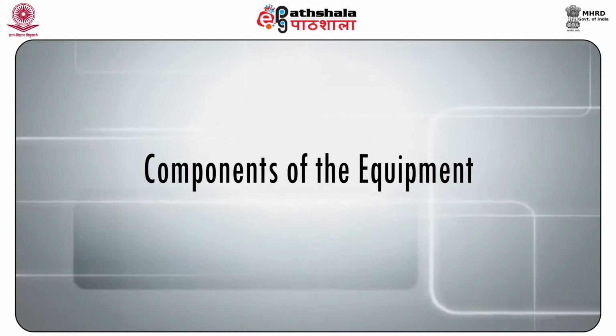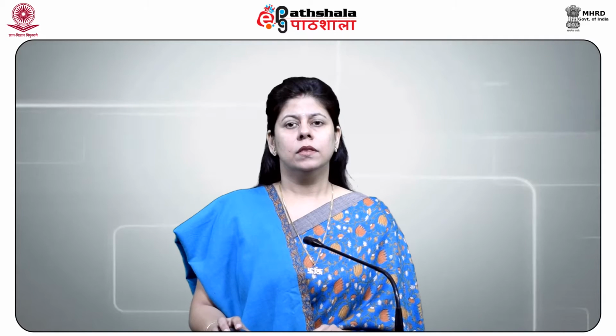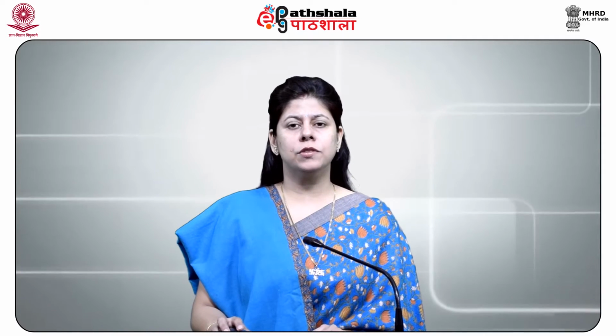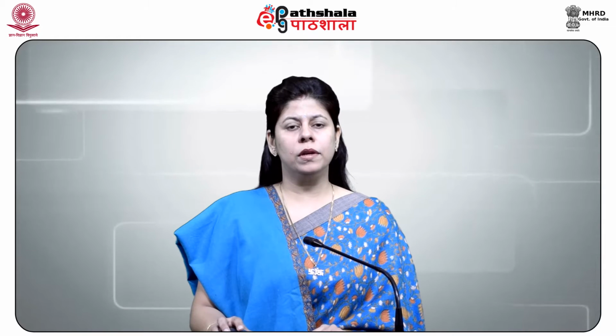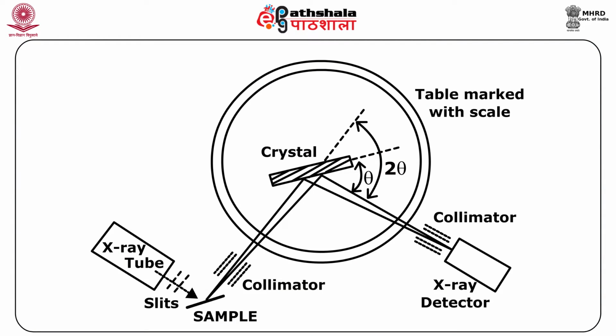Components of the equipment. Instrumentation. The schematic diagram for an X-ray fluorescence system is shown in the figure. The filtered primary X-rays from the tube hit the sample and produce the fluorescence radiation characteristic of the elements in the sample. This radiation passes through a collimator and on to the analyzing crystal. The wavelength is determined and recorded as the synchronized detector rotates in an arc around the analyzing crystal.